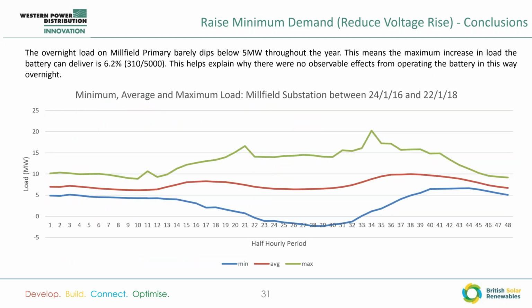So, looking into why we're not seeing the effect that we wanted, the overnight load on Millfield Primary barely dips below 5 megawatts throughout the year. So on the most lightly loaded day of the year, overnight, you've got 5 megawatts of load going through those transformers. So the battery can add 6.2%, which is not enough to make any reasonable difference to the overall voltage of the network.